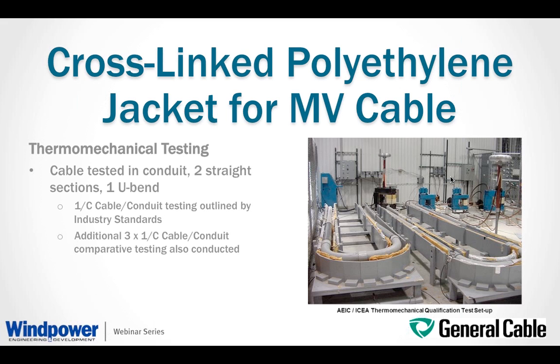Here are the pictures that show the test setup for the thermomechanical qualification testing of ICEA and AEIC. This test is performed on a cable in a conduit. The conduit consists of two straight sections and a U-bend, and the testing that is outlined in the industry standard is normally done on a single one-conductor cable construction. Here we also evaluated the performance of three cables installed in a trefoil arrangement.